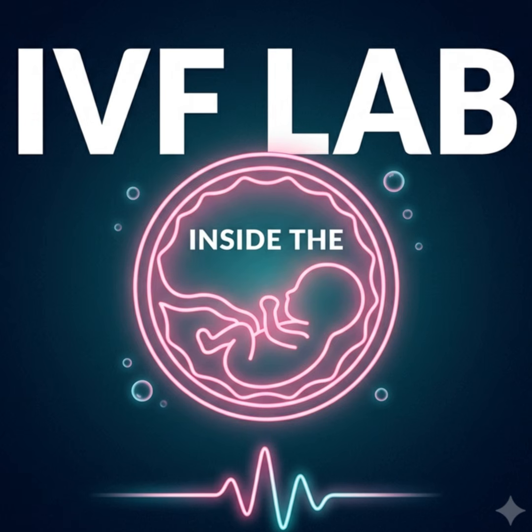The clinical staff will start searching for biological reasons, questioning the culture media or the incubator gas lines, when the reality is a creeping mechanical failure at the workstation. The absolute, unyielding mathematical precision of the micromanipulation machinery is the silent anchor of the laboratory's clinical success. If the anchor drags, the entire operation drifts into failure.